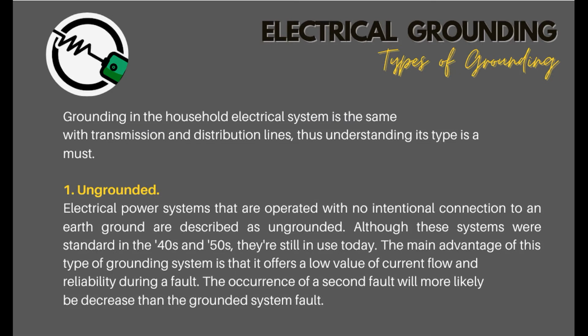Types of grounding. Grounding in the household electrical system is the same with transmission and distribution lines, thus understanding its type is a must. 1. Ungrounded. Electrical power systems that are operated with no intentional connection to an earth ground are described as ungrounded. Although these systems were standard in the 40s and 50s, they're still in use today. The main advantage of this type of grounding system is that it offers a low value of current flow and reliability during a fault. The occurrence of a second fault will more likely be decreased than the grounded system fault.